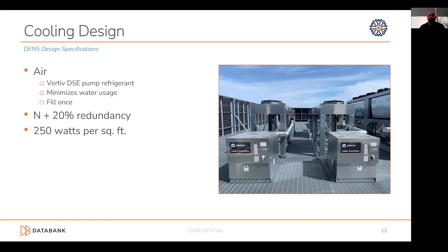From a cooling perspective, this is one of our sites where we've deployed the Vertiv DSE cooling technology — air-cooled, pump refrigerant, with minimal water usage. Our standard design is N+20 from a redundancy perspective. We're looking at 250 watts per square foot per data hall from a density perspective. We have also deployed the Vertiv XTM solution for higher density clients looking for chilled water back doors.